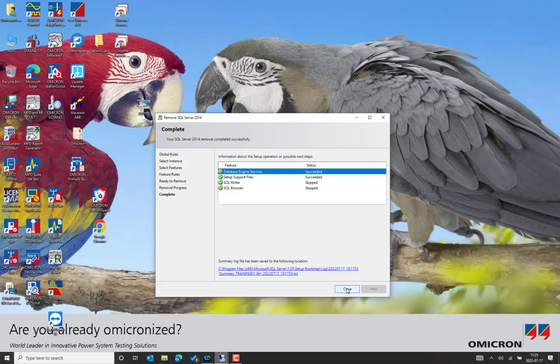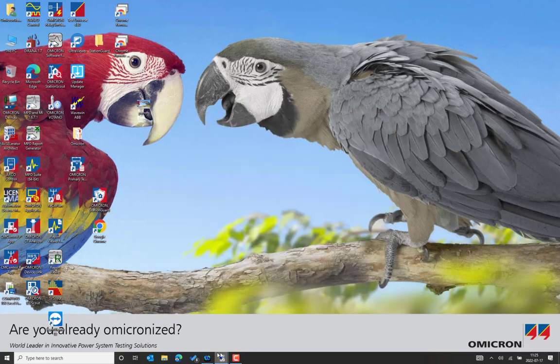This is very important to do properly on a PC with an older PCM 600 installation so that when you install a newer version, it works correctly. Note that PCM 600 does support parallel installation — you can have an older version installed and then install the latest version on top of it. However, if you've decided you no longer need the older version, it is highly recommended to uninstall it properly by removing the SQL Server instance. Click Close.